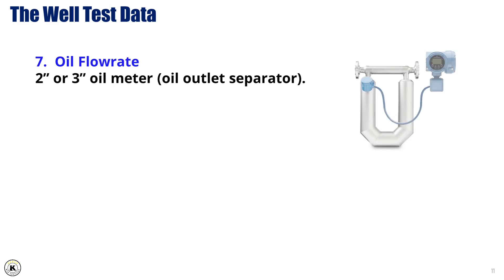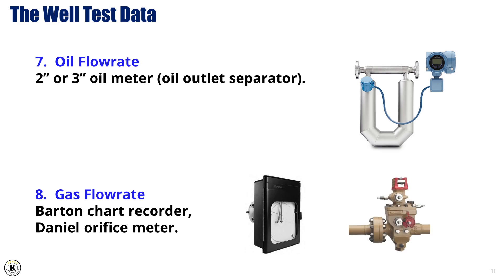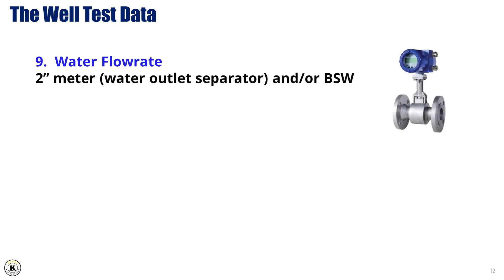7. Oil Flow Rate — measured using a 2-inch or 3-inch oil meter at the oil outlet from the separator to determine the volume of oil being produced. 8. Gas Flow Rate — measured using a Barton chart recorder with a Daniel orifice meter, which calculates the gas flow rate based on a pressure drop across the orifice in the gas flow path. 9. Water Flow Rate — measured using a 2-inch meter at the water outlet from the separator; it can also be calculated using the BSW.